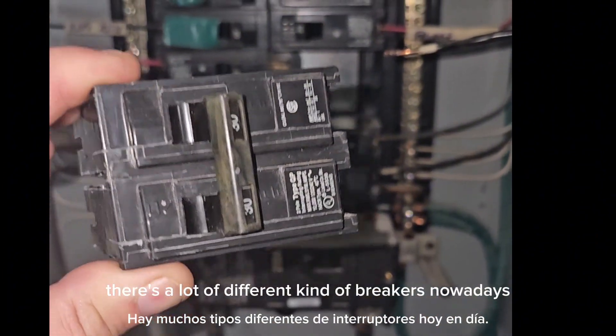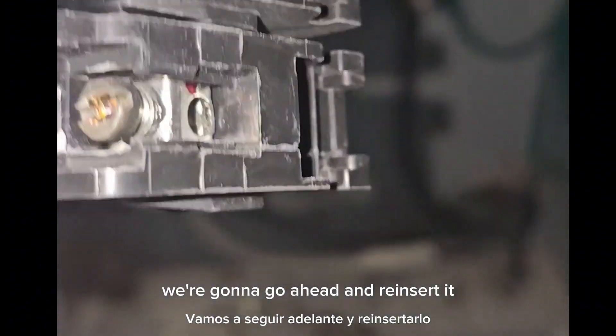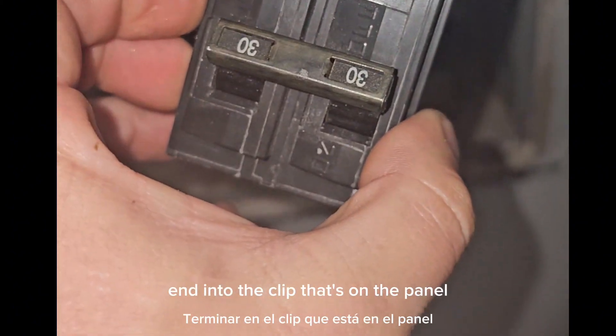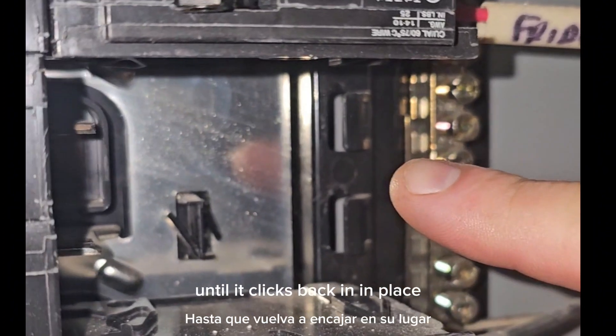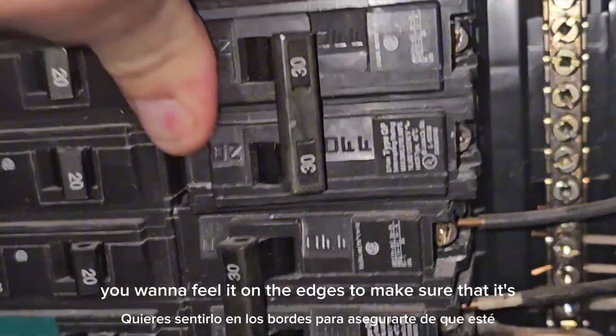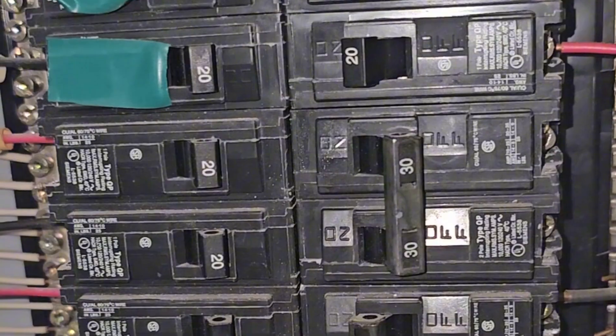There are a lot of different kinds of breakers nowadays. Now that you have your correct replacement breaker, we're going to go ahead and reinsert it. What we do is hook this clip end into the clip that's on the panel, and then give it a good amount of pressure until it clicks back into place. Once it's in place, you want to feel it on the edges to make sure that it's flush with the surrounding breakers.